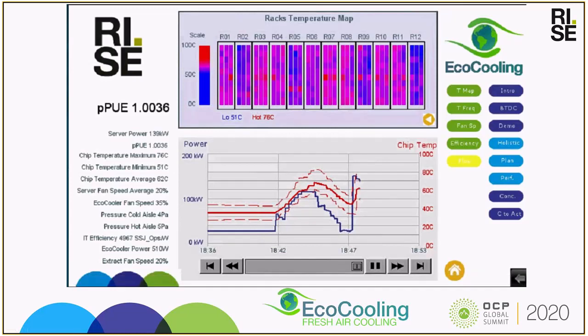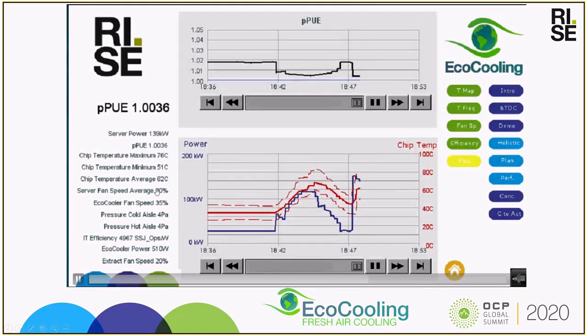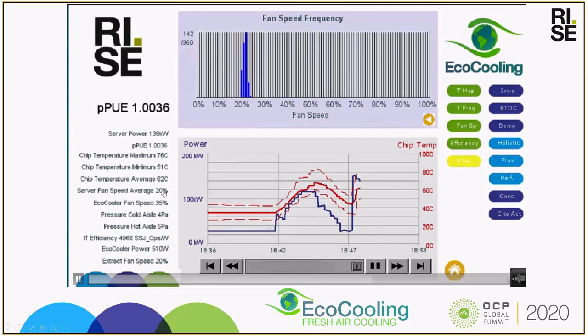Server fan speeds haven't really changed much. The histogram has slightly moved to the right, but the average is still rounded to 20%. The eco-cooling fan speed is 35%. The extract fan is still at 20%. But you might be able to see the histogram slightly moving towards the right now as this persistent heavy workload sits on the data center. And we're using peak 140 kilowatts.